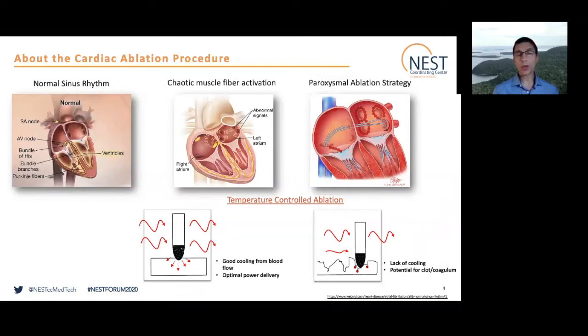And in order to do this, because the catheters that we'll be talking about today use heat from radio frequency, it's important that there's good cooling. Usually, if the tissue is flat, there's good cooling from blood flow, which then leads to optimal power delivery into the muscle tissue to ensure that a surface ablation can be made that really stops the asynchronous muscle signal from creating chaotic muscle contractions in the heart. However, in certain types of tissue where there may be pockets or valleys, there may be lack of cooling, and then when the heat is applied for the ablation, it creates the potential for a clot or coagulum, and therefore limits the ability of the electrophysiologist who's doing the procedure to deliver the power that's needed to create the isolation of the asynchronous muscle tissue. Next, please.